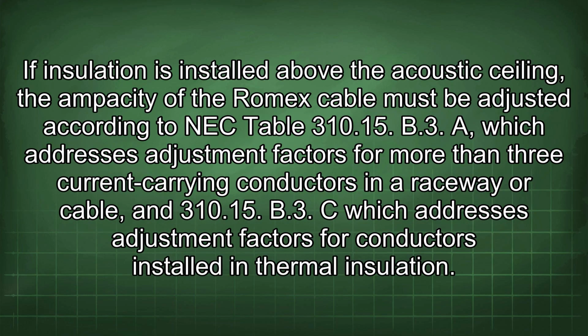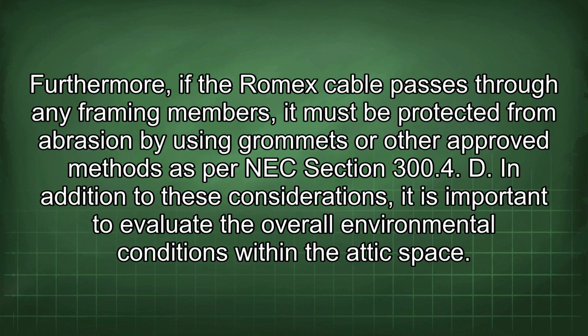Additionally, it is crucial to consider the presence of any insulation. If insulation is installed above the acoustic ceiling, the ampacity of the Romex cable must be adjusted according to NEC Table 310.15(B)(3)(a), which addresses adjustment factors for more than 3 current carrying conductors in a raceway or cable, and 310.15(B)(3)(c), which addresses adjustment factors for conductors installed in thermal insulation. Furthermore, if the Romex cable passes through any framing members, it must be protected from abrasion by using grommets or other approved methods as per NEC Section 300.4.